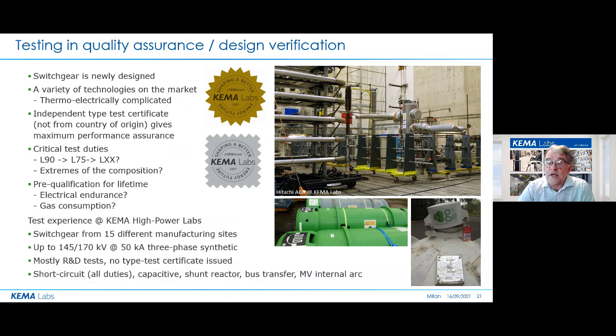In the past 3 years, KEMA has tested switchgear with new SF6-free solutions, apart, of course, from the standard air-insulated medium voltage VCBs, from 15 manufacturer sites up to 170 kV 50 kA in 3-phase synthetic test setups. In last year's COVID pandemic, testing continued even by remote interaction with the design teams at their homes. Almost all tests we have seen were R&D related, with all gas mixtures mentioned in this talk and with all short-circuit and switching test duties that are in the standard.